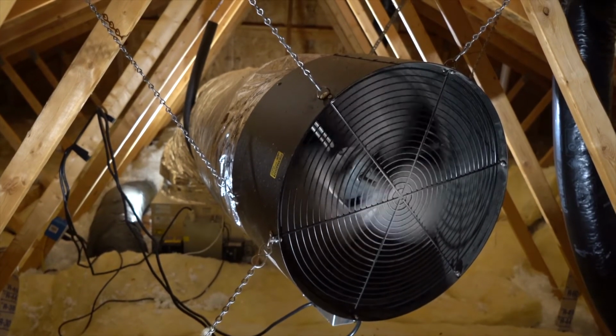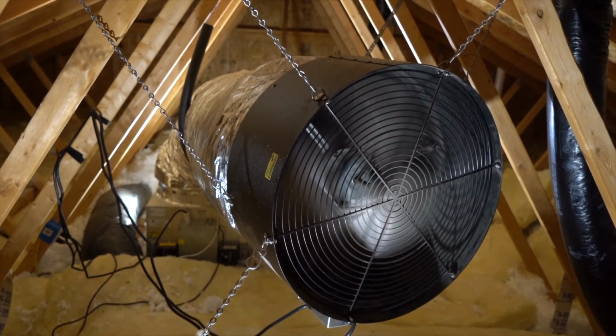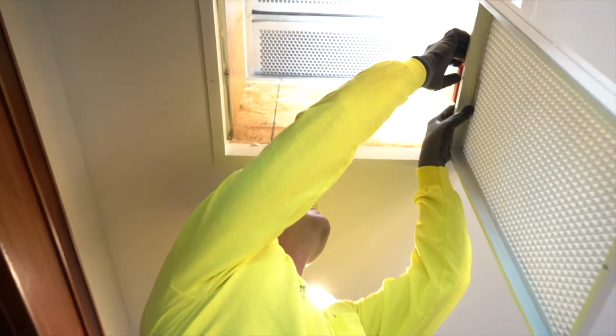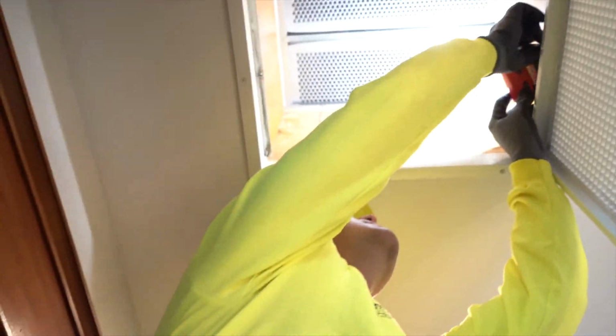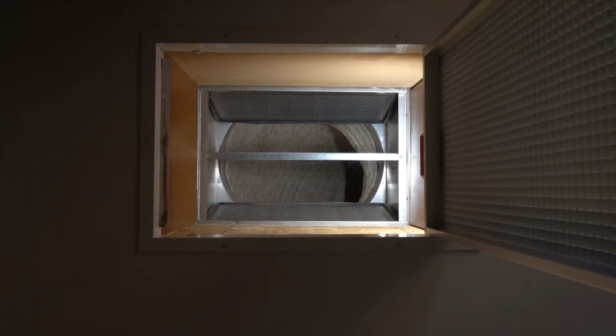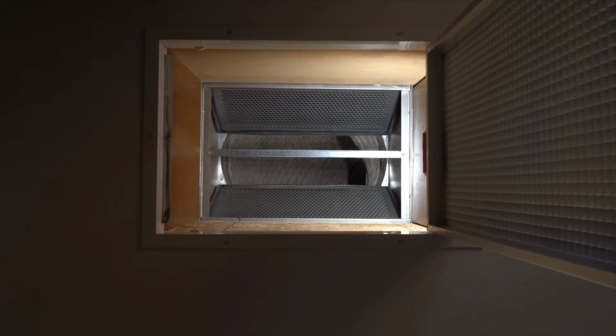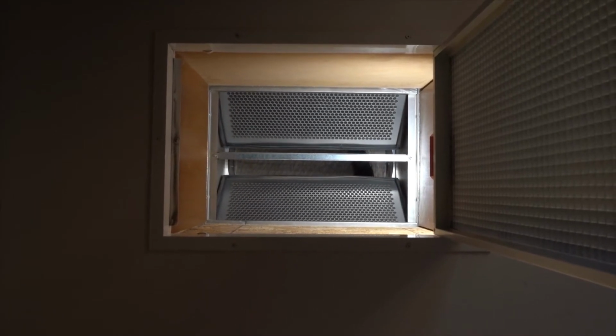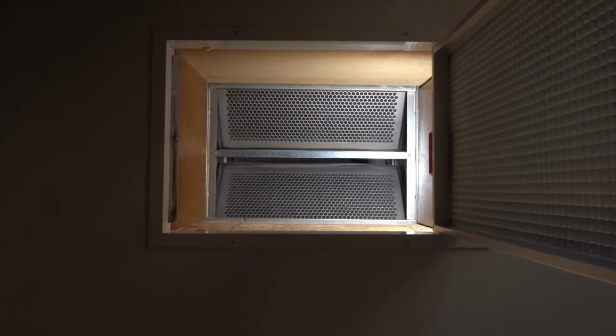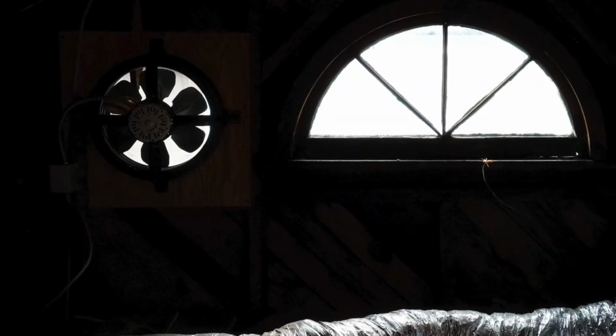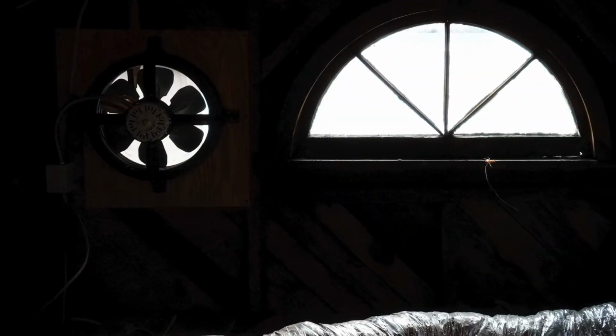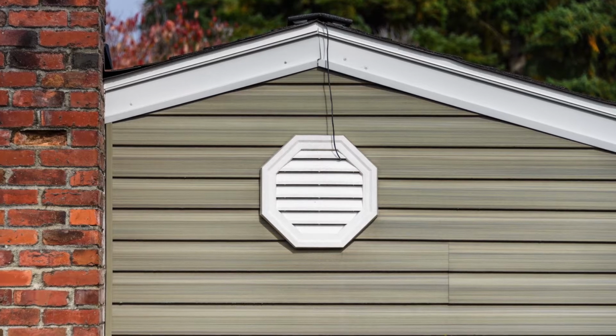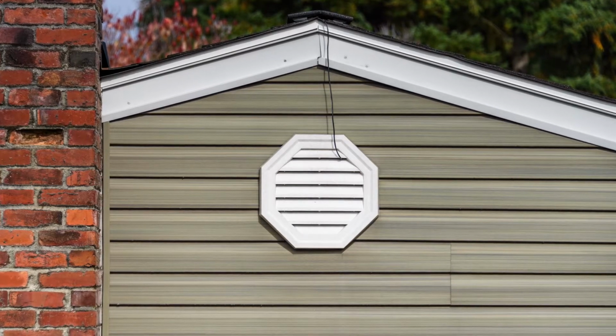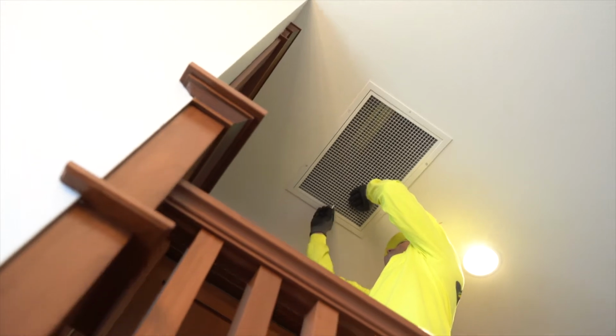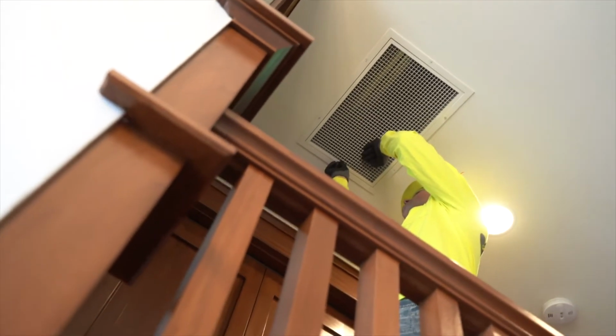And location, it's not necessarily an outside wall. It can be inside or anywhere, correct? Definitely. For the whole house fan, you want to set it up basically inside a wall, mostly a ceiling, inside the house somewhere. There's another means, an attic fan, which works a little differently. It just focuses on the heat in the attic, venting out either an outside wall or through the roof, controlled by a little different means. But the whole house fan is normally very specific to an inner wall or the ceiling, and then vents out in the attic, creating pressure and pushing it out through your soffit.